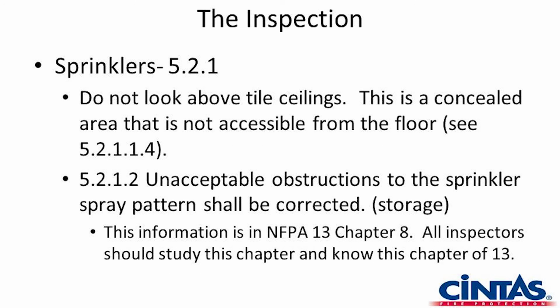Chapter 5: do not look above tile ceilings. Now, these aren't rules that tell us that absolutely, positively, if we're doing an inspection, we can't do these things, but they exist to make sure there's consistency through all inspections. We talk about inspecting from the floor and other items. Again, NFPA standards are the minimum standards, so they make sure we're doing at least the minimum amount of work to try to find issues within the building.